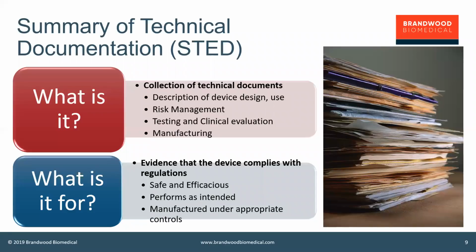And so that collection of technical documents will include any description around the device design, your risk management strategy, plan, report, any of the hazard analysis, FMEAs, things like that, your testing and clinical validation, and then any manufacturing summary. So that is the content that goes into that STED. And like I said, ultimately, in that STED, you are trying to show evidence that your device complies with the regulations.